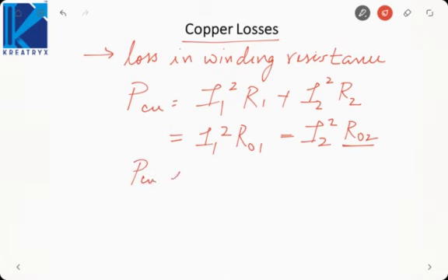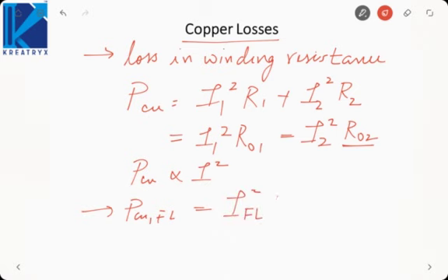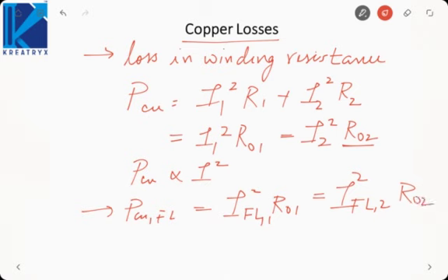Copper loss is proportional to current squared. At full load, it is I_FL1 squared into R01, or I_FL2 squared into R02. Transformers may not always operate at full load — distribution transformers near homes operate at variable load. In the daytime we may not switch on tube lights, but at night we do, so the load varies. Loading is defined as I = X times I_fullload, meaning X percent of full load implies the current flowing is X percent of the full load current.